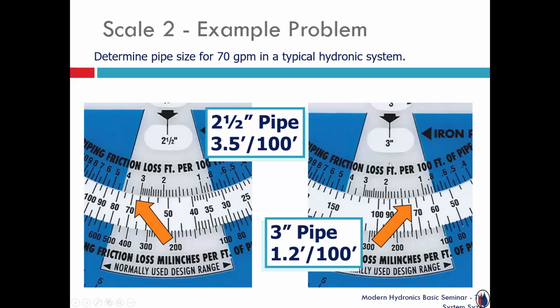And some of the charts that ASHRAE will publish, and I think we even had it at the end of the last session's presentation in the PDF form, they talked about hours of operation, less than 2,000, 2,000 to 4,000, whatever. You might get into bigger pipe because you're running for longer, consuming more energy, so use a larger diameter pipe. Yes, more expensive up front. Overall operating costs might be more favorable, if you will.